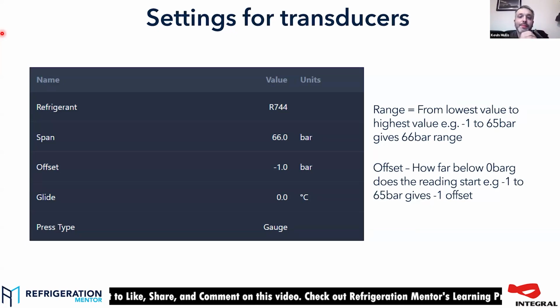So as per my notes there, span in this is the full range of the transducer. So for an R744 transducer, you might have -1 to 65 bar. So that transducer has a span of 66 bar. If you just set that it only goes up to 65 bar, you're going to have an incorrect calculation.